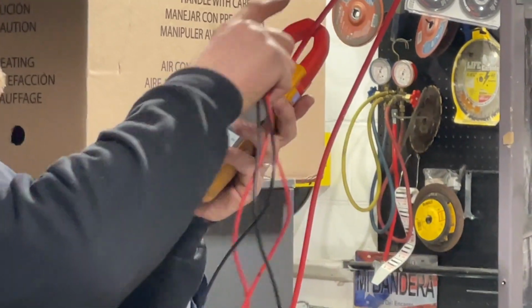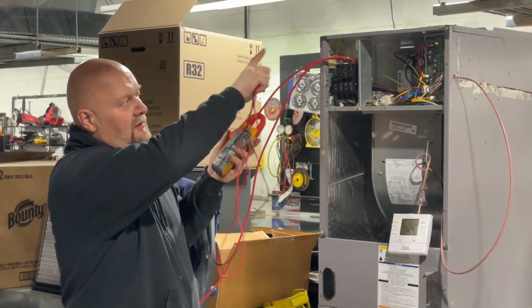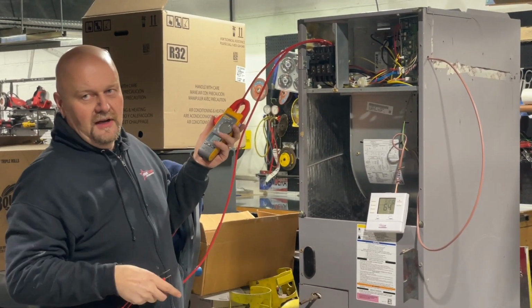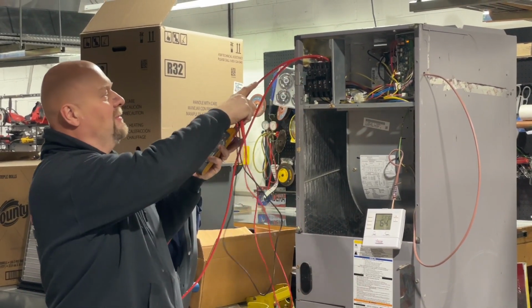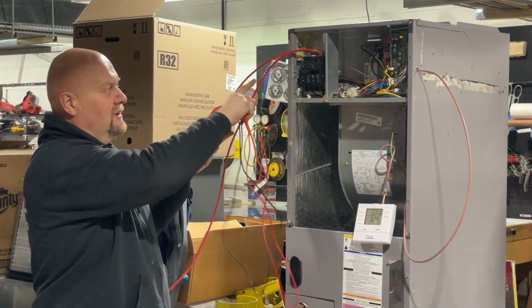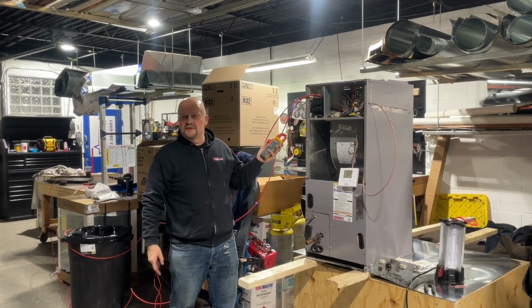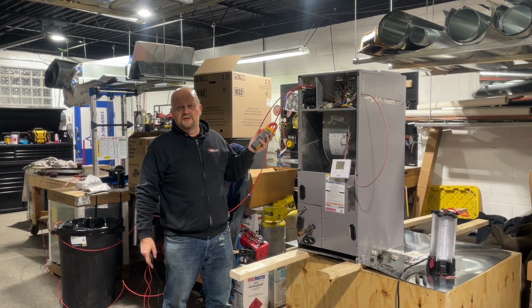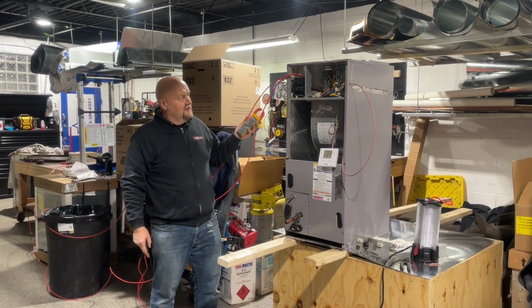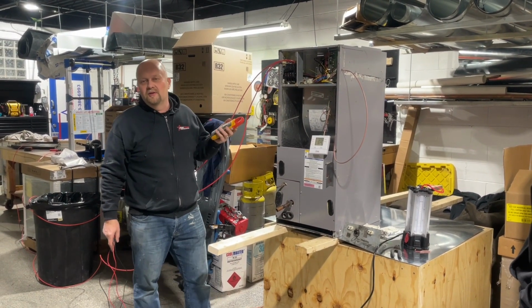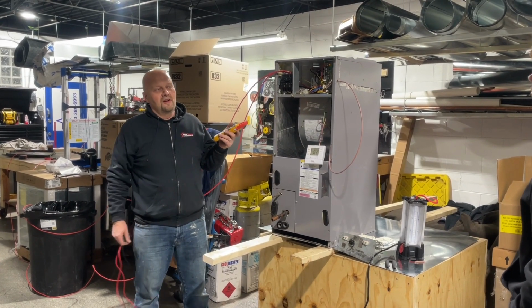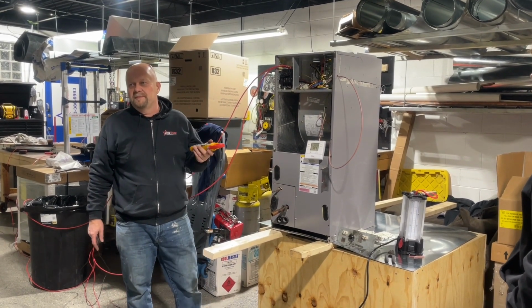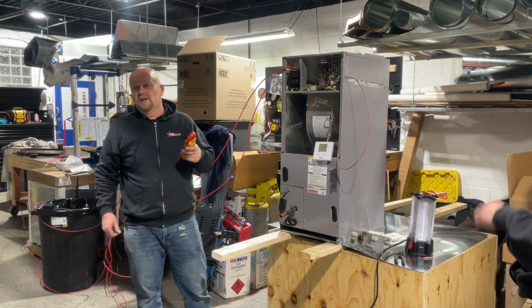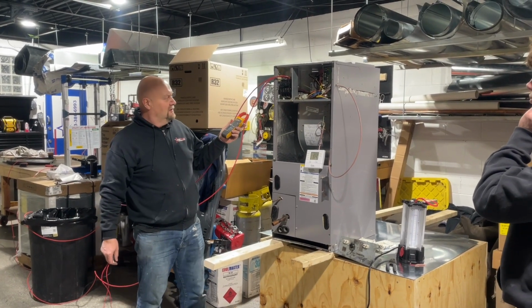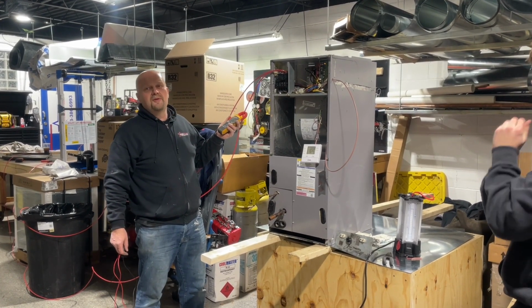That's because these two are part of a circuit. You're basically feeding Mr. Electrons from both sides and they're running backwards, right? The Mr. Electron from here is going to run through the heaters, come back, run this way. Mr. Electron from this feed is going to go through a circuit and run back on the opposite leg. That means that you're not adding the amps that you measure on both of these legs, it's basically whichever one you're going to get, this is what you have. So right now we're drawing 40 amps, and you're going to notice that we have a 60 amp circuit breaker here, right? So typically protection is going to be about 80%. Sorry, the usage is 80% of protection. So if you have a 100 amp circuit breaker, you're going to draw about 80 amps, right? If you have a 60, you're going to draw 30 to 40. So we're drawing 40 amps. So now we know that this is working.